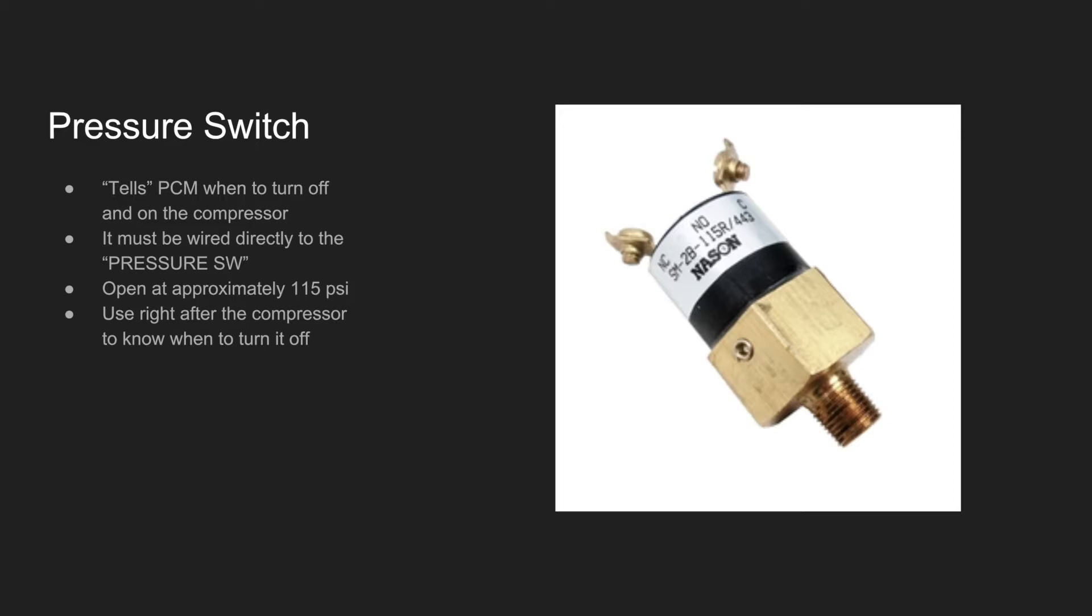It stops at approximately 115 psi, and it's used to tell the compressor when to turn off so it doesn't keep flooding the system with compressed air. For that reason, it's usually put right after the compressor.